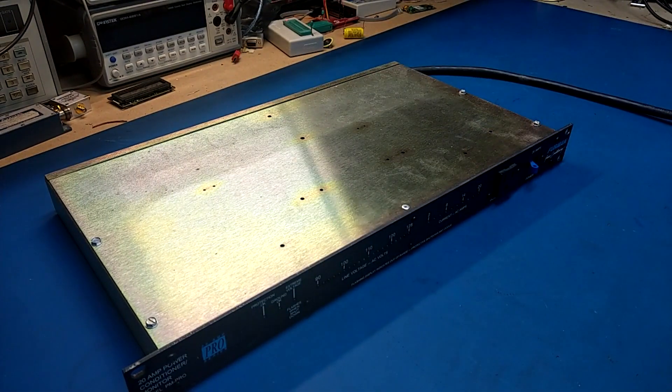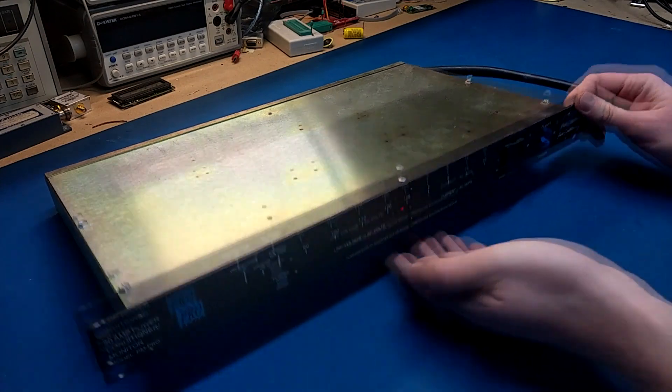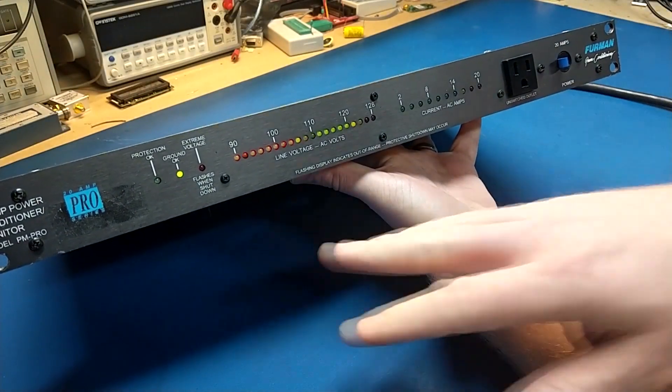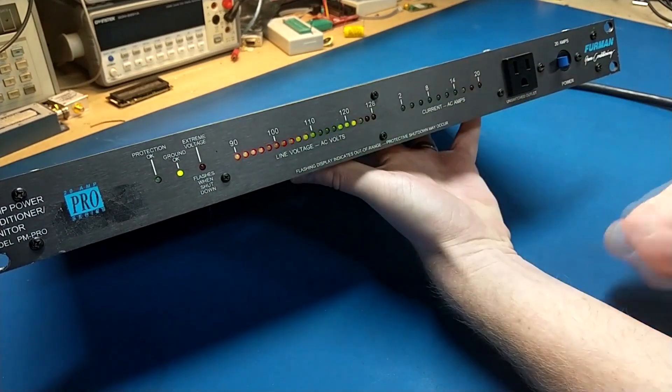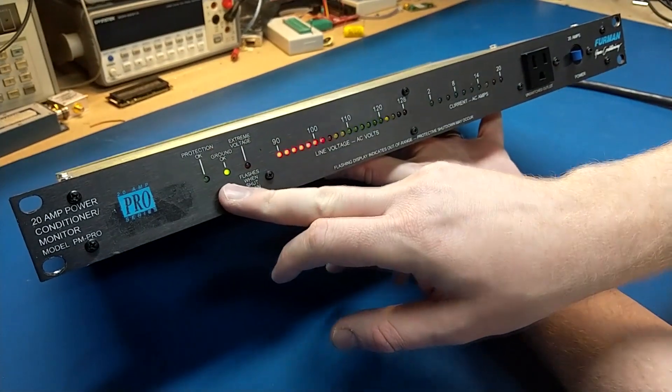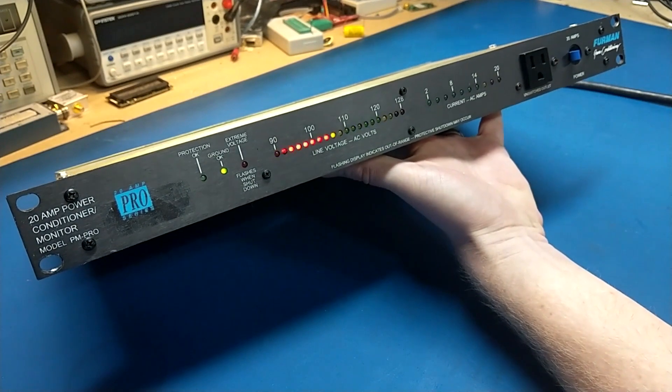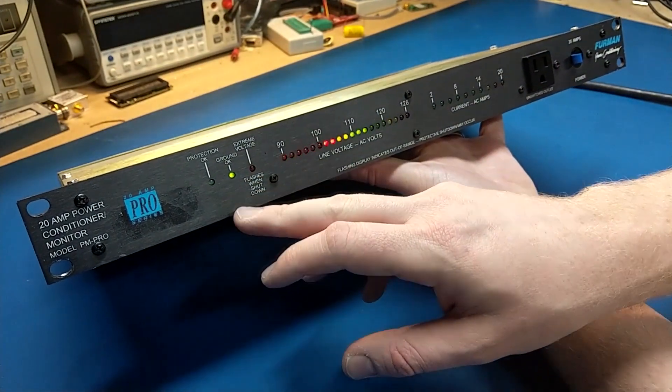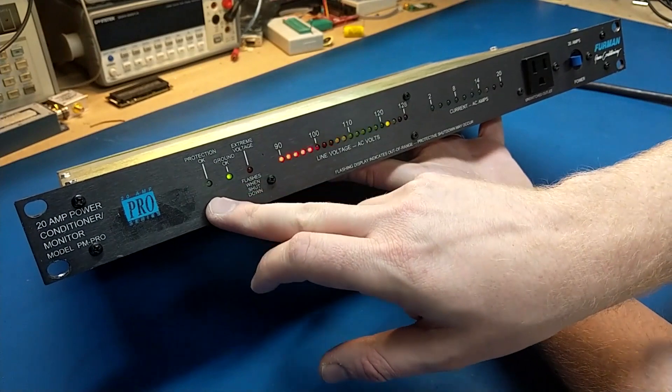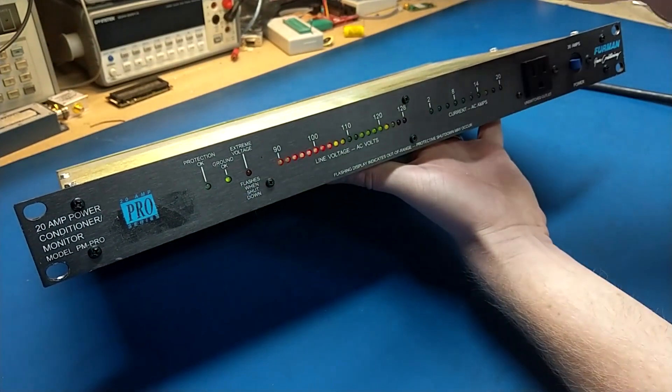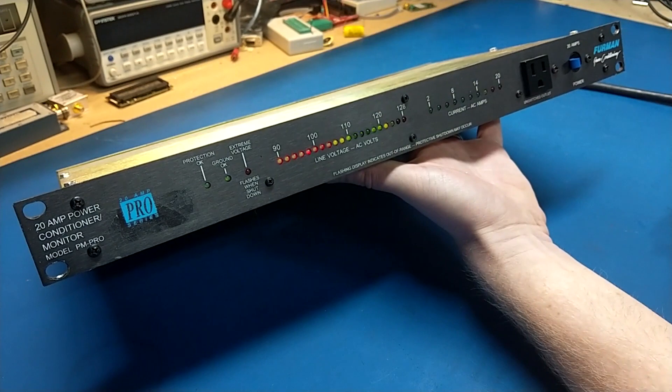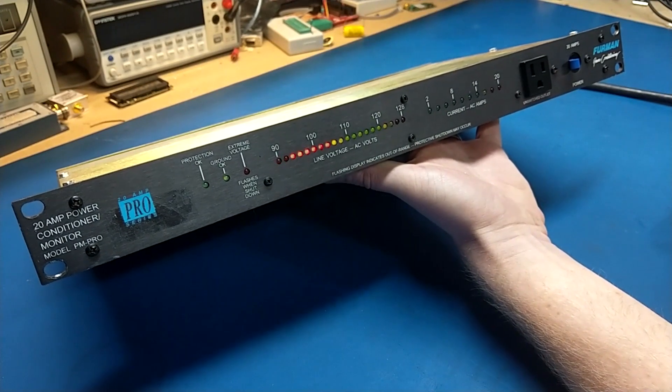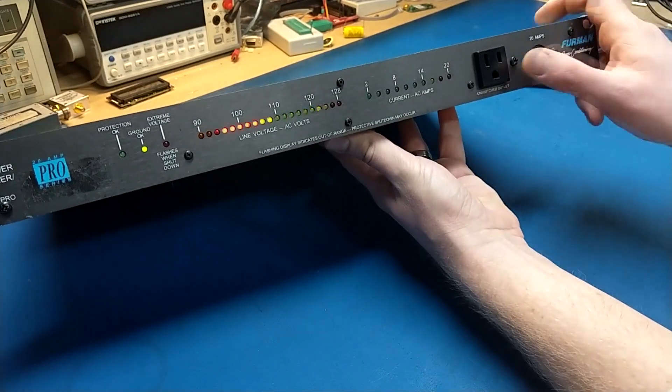I'll plug it in real quick. It does a little dance there as it powers up, and then you can see it displays your current AC voltage going in there. Ground okay. I've actually got this plugged into an outlet, not my Variac, because the Variac actually lifts the ground so that wouldn't be lit plugged into there. And then you notice the protection okay light is not on, which clues me in that this is probably taking a hit and it's probably either got some blown fuses or blown MOVs, or possibly both inside.